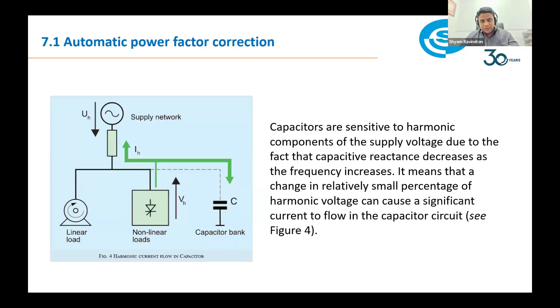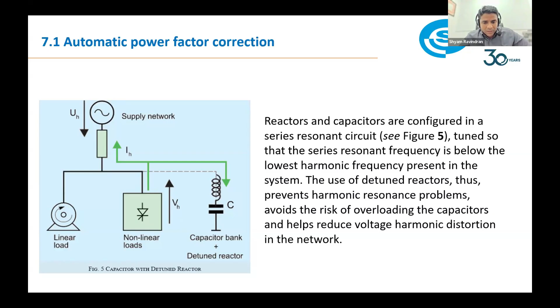The market knows this product, and I have even seen it installed in many customer premises, called passive filters or detuned filters. The reactors and capacitors are configured in a series resonance circuit, tuned so that the series resonance frequency is below the lowest harmonic frequency present in the system. The use of detuned reactors thus prevents harmonic resonance problems, avoids the risk of overloading capacitors, and thus reduces voltage harmonic distortion in the network. So these systems were also available.